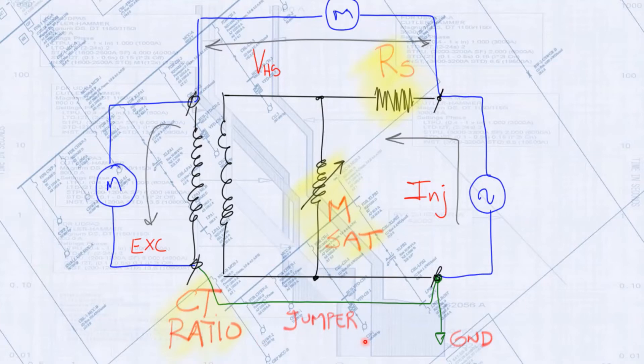In field testing applications where a ground grid is available, a grounding jumper is connected between the H2 and X2 terminals for safety and insulation testing reference. With this arrangement, testing readings are recorded for estimation of ratio, saturation, and secondary winding impedance.